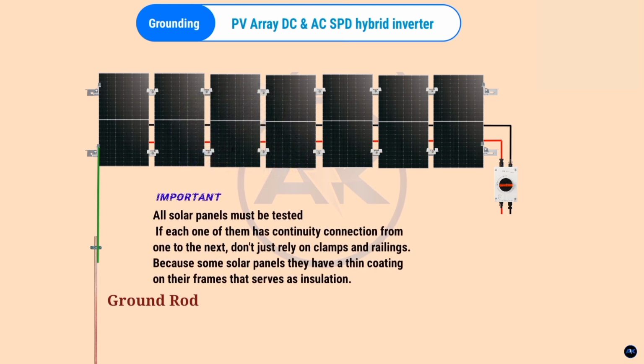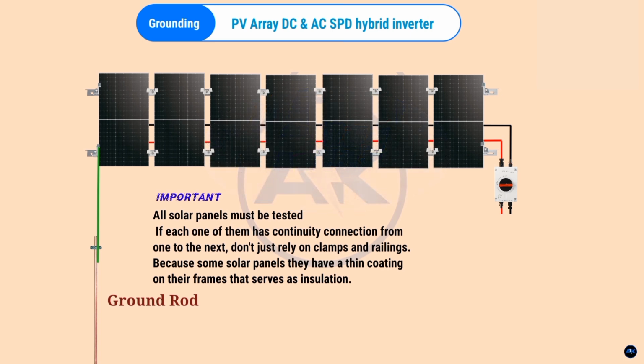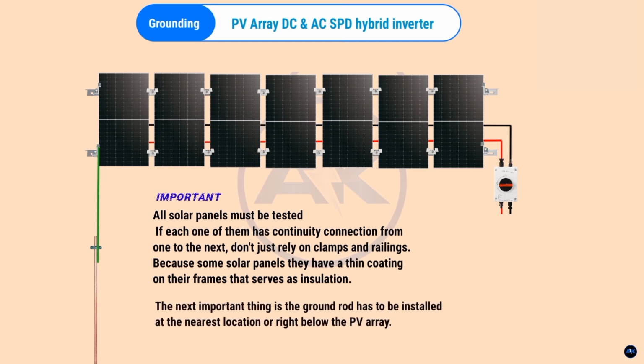All solar panels must be tested to see if each one of them has a continuity connection from one to the next. Don't just rely on clamps and railings, because some solar panels have a thin coating on their frames that serves as insulation. If needed, bond all PV panels using copper wire. Now you don't have to do this if you are 100% sure that all the solar panels have continuity to each other. The next important thing is the ground rod has to be installed at the nearest location, or right below the PV array.